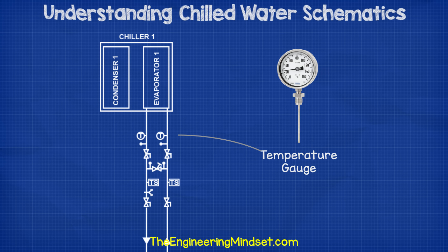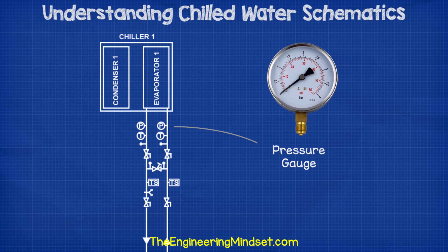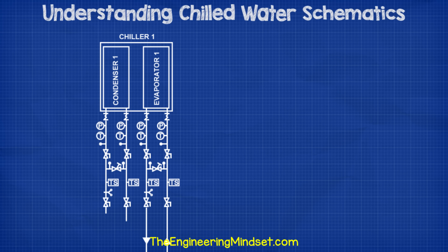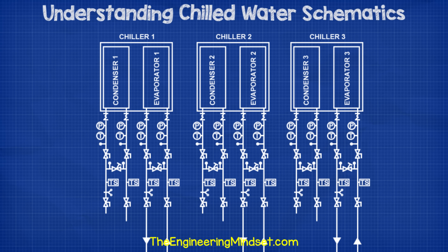Then we'll have some temperature gauges to manually take readings — over time these generally become less reliable and the gauges often get stuck. Then we'll have some pressure gauges to allow manual readings, which can also become less reliable over time. Then we'll have some flexible connectors, which prevent the vibrations of the pumps and the chillers from running along the pipes throughout the building, and they also allow the pipes to expand and contract slightly, which takes the pressure off the connection. We'll usually find an almost identical setup on the condenser side. This design is for a large commercial office building, so there will be multiple chillers, and all of them will have identical pipe arrangements.